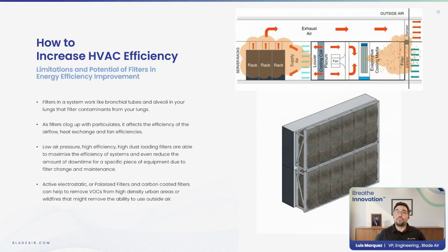So the secret is to use low pressure filters with high dust holding capacities. With these, you're able to maximize your existing efficiency, and more importantly, you're able to keep that maximized efficiency longer. Many of these specialized filters, like polarized filters or active electrostatic filters, can help remove VOCs and increase dust holding capacity. That can help even in the event of wildfires or other contaminants that may prevent the use of outside air. Obviously, we know wildfires are more and more prevalent, and we know that they have high quantities of VOCs and 10 times the pollutant concentrations. And without these filters, oftentimes it would prevent you from using that outside air without risk of damaging your equipment.